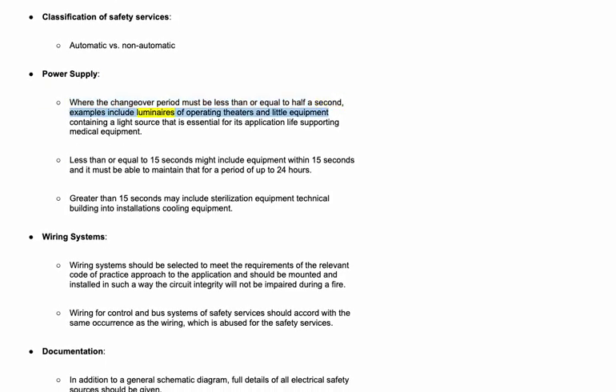Examples include luminaires of operating theaters and equipment containing a light source that is essential for its application, life supporting medical equipment. Less than or equal to 15 seconds might include equipment that must operate within 15 seconds, and it must be able to maintain that for a period of up to 24 hours. Greater than 15 seconds may include sterilization equipment, technical building installations, cooling equipment.